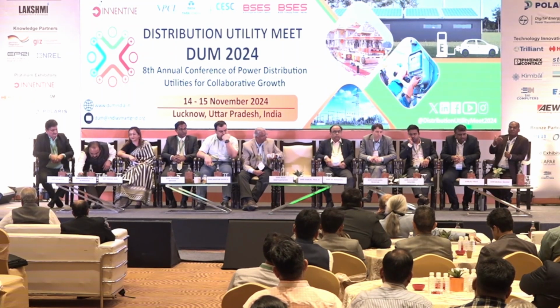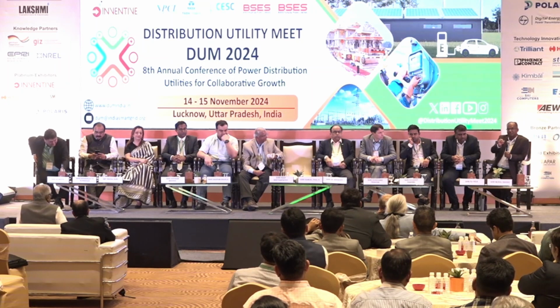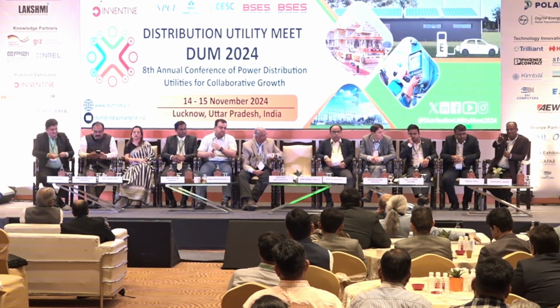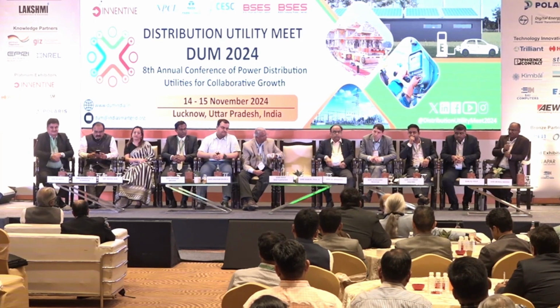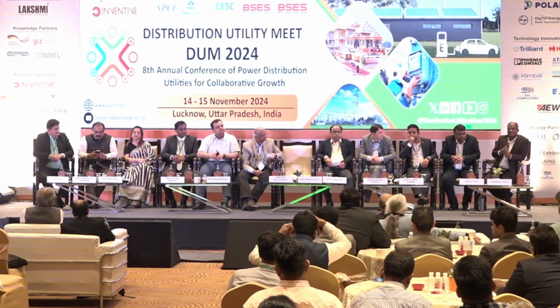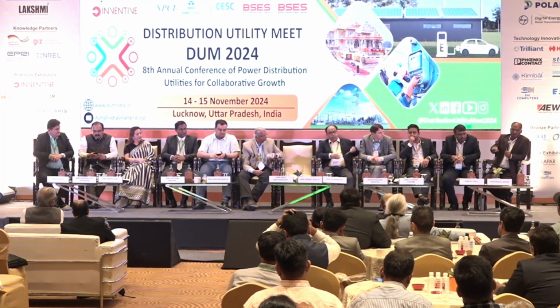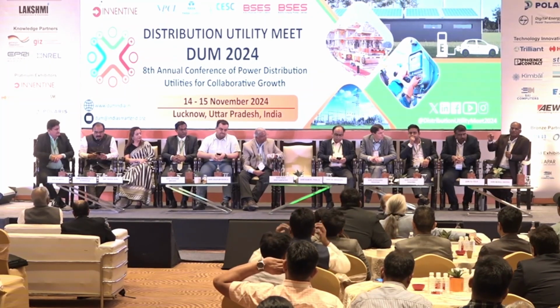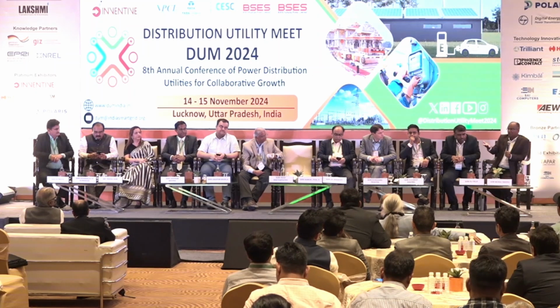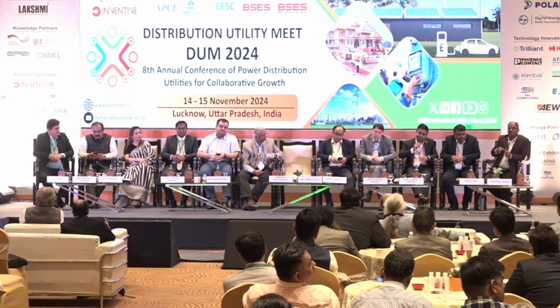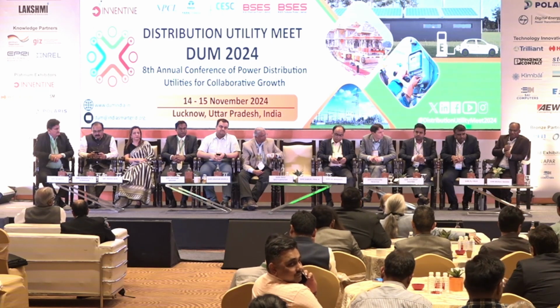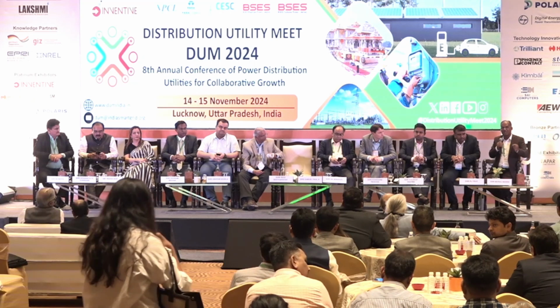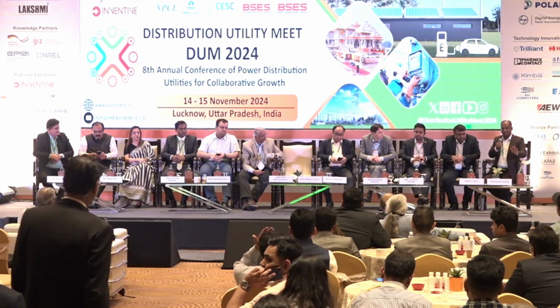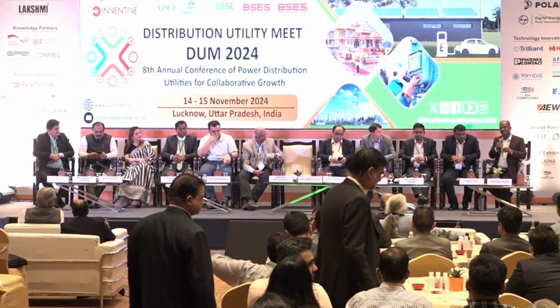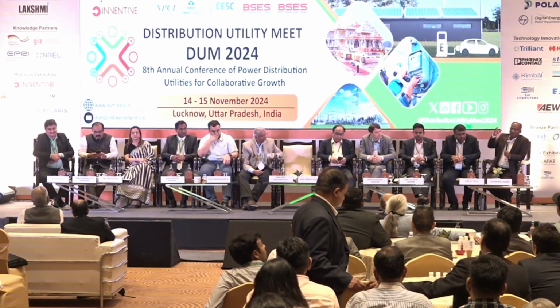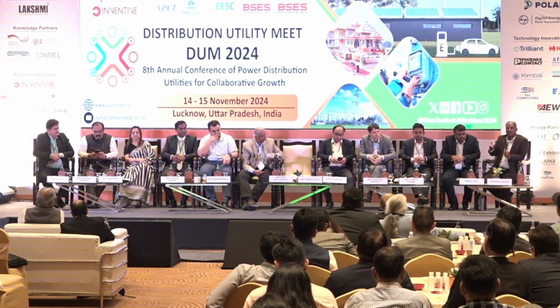Then we realized there's a lot more proliferation of inverters, and these can actually benefit the grid a lot better—disconnecting them doesn't really help the grid. That's where the 2018 version of 1547 says they should stay connected, ride through faults, and also provide voltage and frequency support. I think that's what we're getting to—we need to demonstrate that with a few pilots with utilities and see how it goes. There are other issues, safety concerns, but I think we have a way to take care of it. It's not about the capability of the inverters, they can do that, but there's a lot we need to go through, because our normal legacy way of operations probably won't work with what inverters can do.